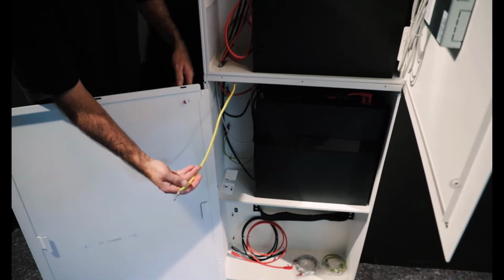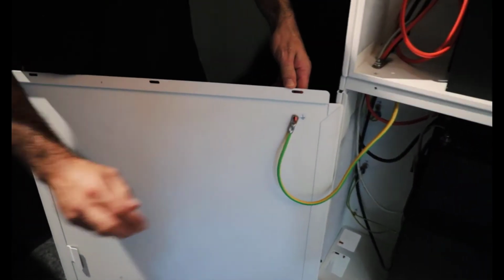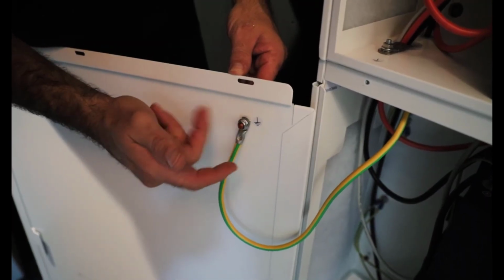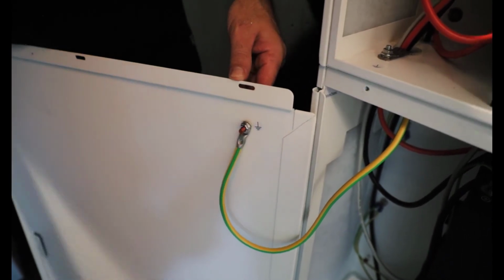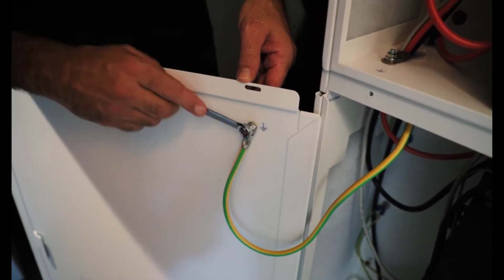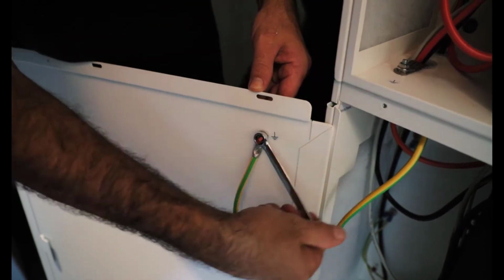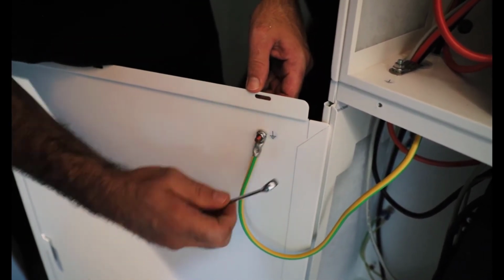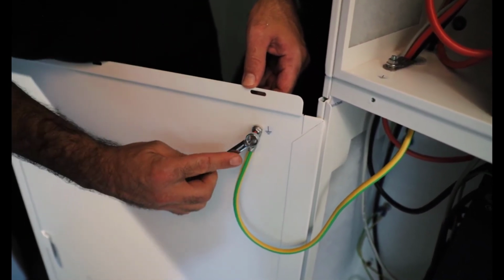The door itself also has an equipotential bonding strap which goes onto the door. Make sure that that's nice and tight, and also just make sure that it's positioned in such a way that it allows you to be able to close the door. Sometimes if you have that lug facing upwards or to the side, it can be a bit tricky to close it.